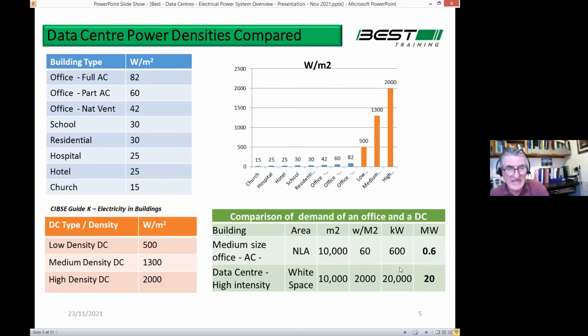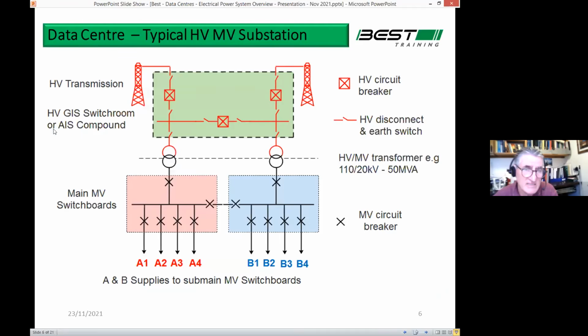So you can't just get onto the ESB and say, listen, I'm building a data center, can you give me 20 megawatts? And they make a connection under the pathway. It doesn't work like that. When you get to 20 megawatts, you have to take power directly off the transmission grid. So that's the big difference. Whereas anything at 0.6 megawatts, you're coming off the medium voltage network. At 20 megawatts, you're at transmission level. So you're connecting at 110 or 220 kV, sorry. So that's what we're talking about.